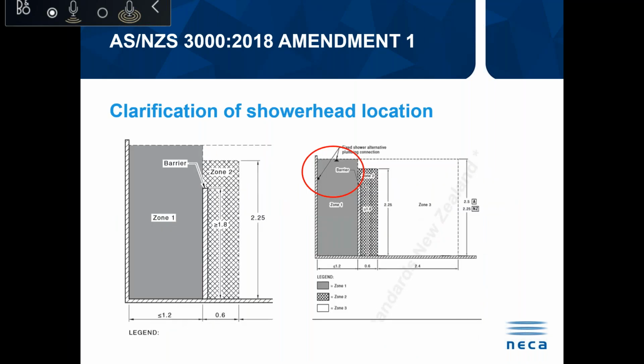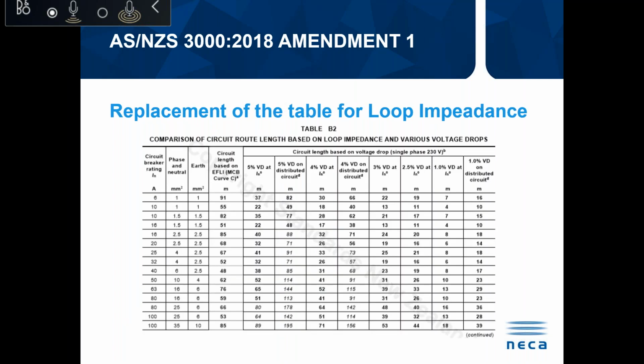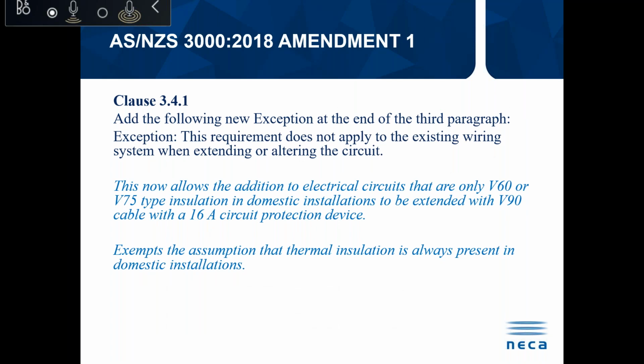A lot of the other changes within Amendment 1 were just slight changes to identify some of the things that were missing in the drawings. So with this drawing here, the fixed shower alternative plumbing connections were not indicated on the drawings on the left. So in Amendment 1, it shows that it covers the ceiling mounted plumbing fixtures as well as the wall mounted fixtures. They've reintroduced the table for fault loop impedance with the circuit protection devices and circuit lengths, which is very handy for working your calculations out.